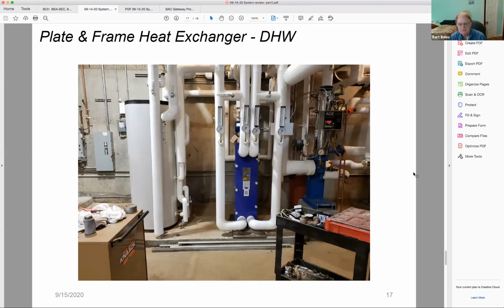One thing to note about the district steam is that it's not clear in the energy metrics that we're seeing how the steam is being treated, whether it's being treated as an energy input, or whether it's being considered as free energy and not being considered as an energy input. It of course should be considered as an energy input, because it is something that requires energy to make, even if it's part of a cogeneration plant, combined heat and power plant. This is how the hot water is made. It's a plate and frame heat exchanger, and then a domestic hot water is sent around the building. Okay.